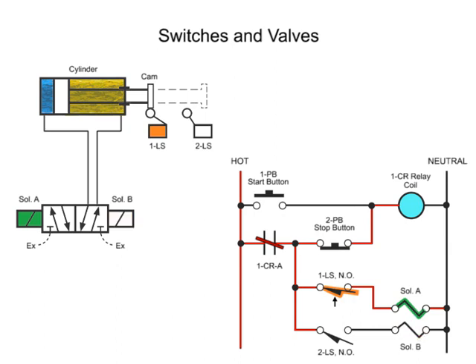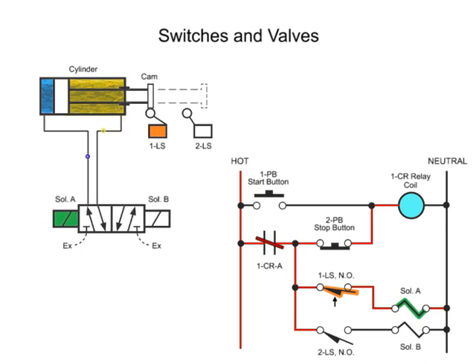Solenoid A operates the hydraulic valve which shifts to allow fluid to flow and extend the cylinder. As the cylinder extends, the cam releases limit switch 1LS which in turn de-energizes solenoid A.